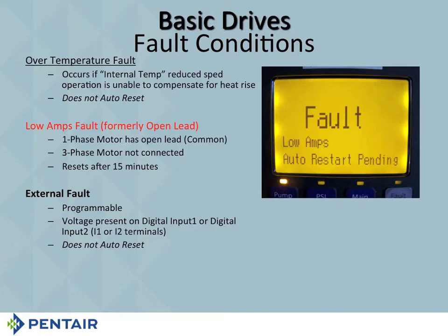External fault, this is where I'm going to program one of those digital inputs. And when I program that digital input for external fault, what I'm saying is, well, let's say, for example, I want to use a moisture sensor. So I put the moisture sensor on the floor. I connect it to input 1. Don't forget, you've got to have a 115 plug out to plug the moisture sensor in, so that way you can send a signal. When moisture hits the 2 contacts down there, it sends a signal up to the drive and says, hey, there's water down here on the floor. You better turn the pump off.